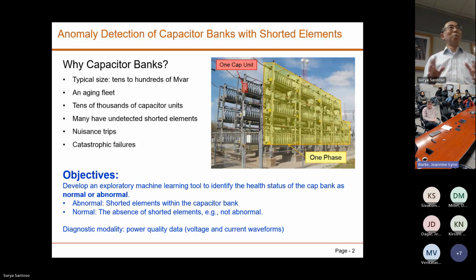What are the impacts of these shorted elements? Sometimes they cause nuisance tripping, and we'll be talking about that. In the worst case, if the tripping did not happen for any reason, it may eventually snowball and lead to a short circuit event, resulting in a full-blown catastrophic failure that destroys the entire capacitor bank.